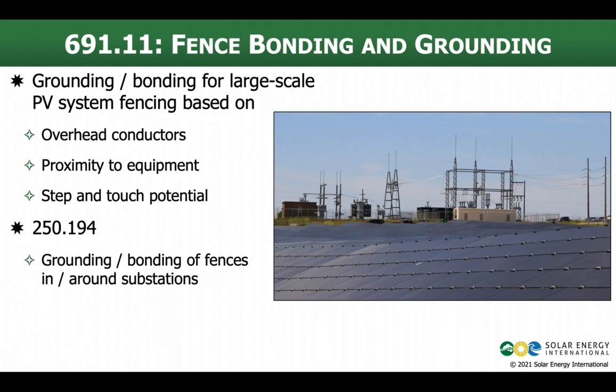And if there's a substation, kind of like the system here, we've got a large PV system, a large scale PV system. It's interconnected via the substation, you can see. Bonding and grounding requirements for fences around the substation, well, there we're going to look to 250.194. So we need to take this into consideration. These need to be documented by the professional engineer. They're going to be part of that stamped plan set.